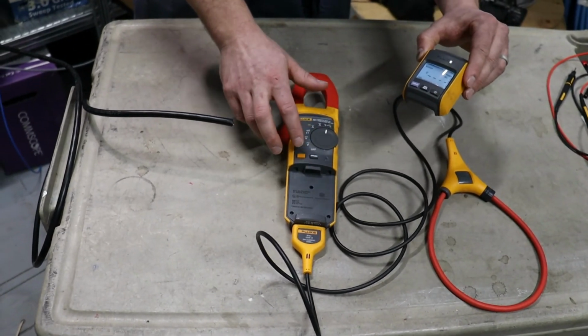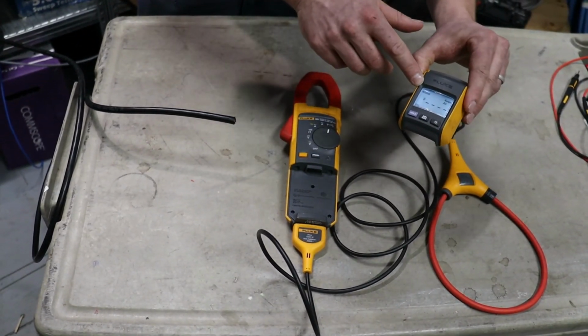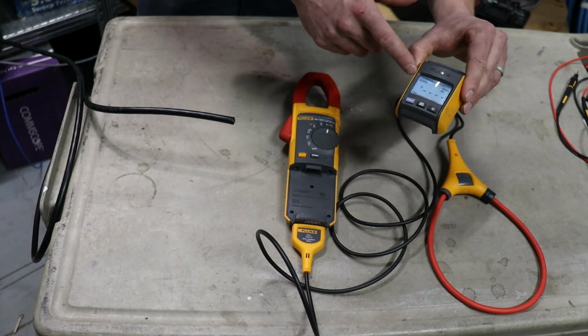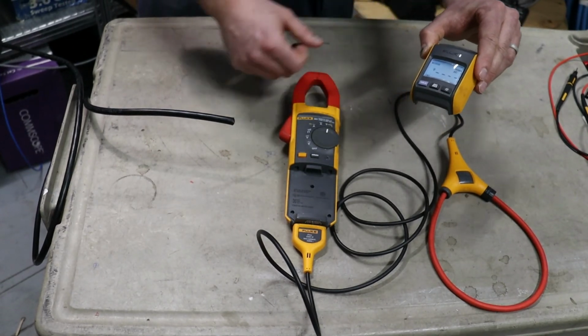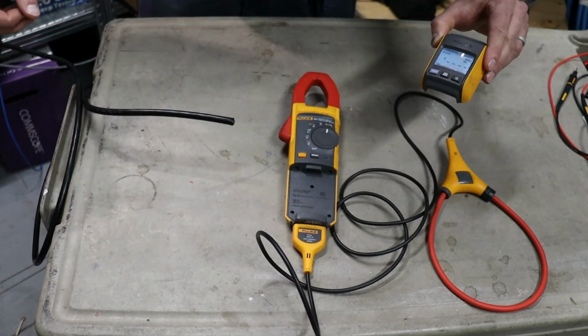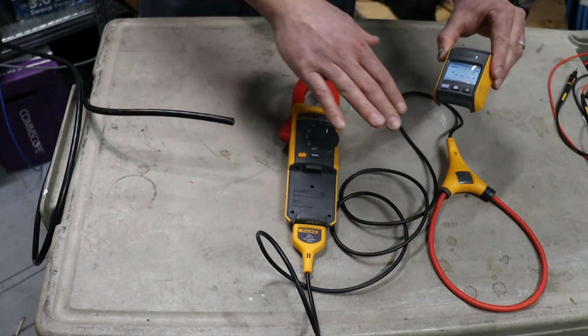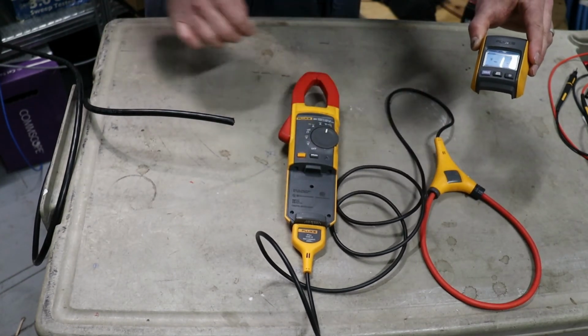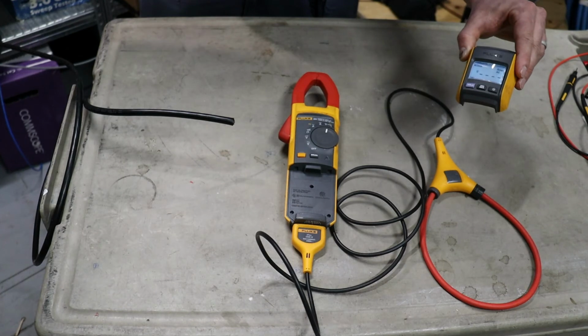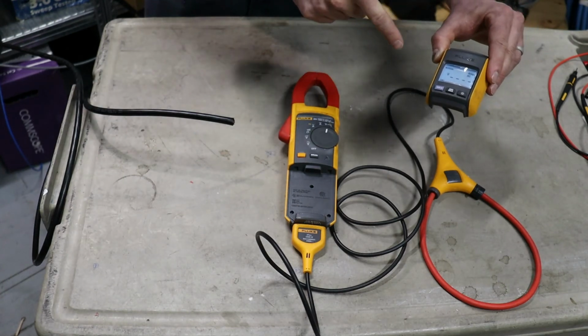You have to press the inrush button. You'll see a little inrush indicator come up on top of the screen, and you're ready to go. If you have this connected around your wire for your motor, go over to your motor starter, press start, and it's going to measure that reading.